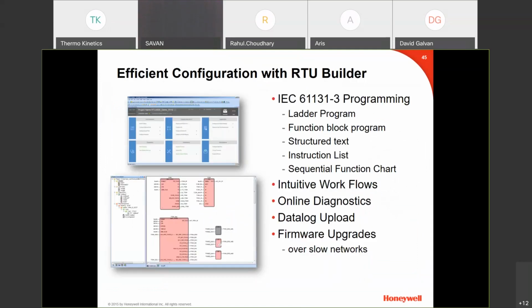Now, when it comes to programming for both the PLC and the RTU, we have the 61131-3 programming IEC. So it's an open standard, and we comply with that open standard. That gives you ladder logic, function block program, structured text, instruction list, and sequential function chart.